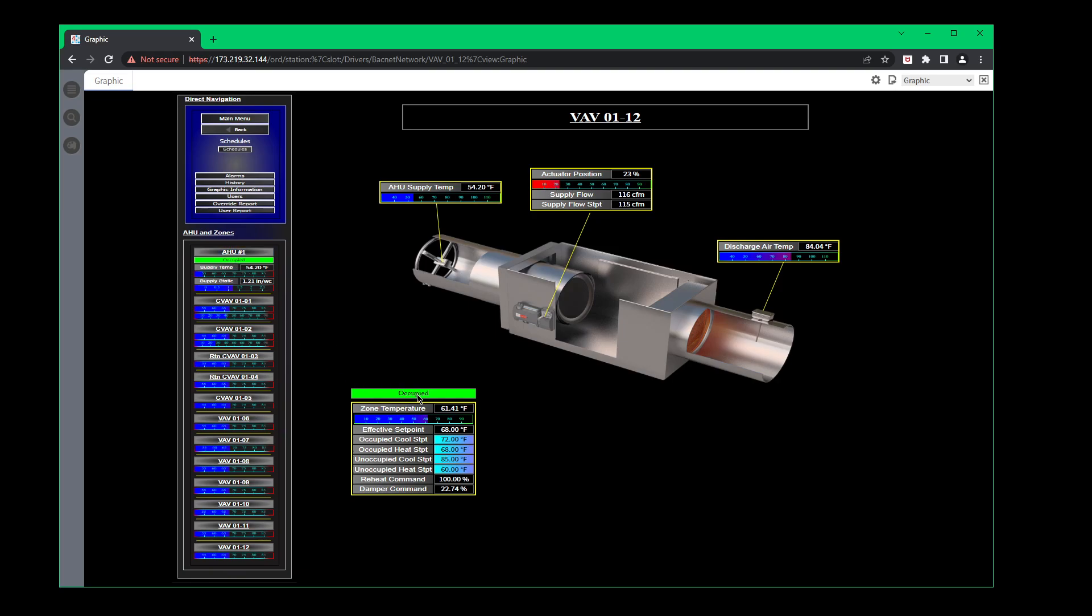Right here is your occupied status, meaning that if you see this unoccupied, that's telling you that your current state, the box is off and it'll control on unoccupied versus the occupied set points. So right now we have a cooling set point of 72, heating set point of 68. Right now the effective set point is 68 because it's trying to warm the space back up because it's 61 in the lobby right now.